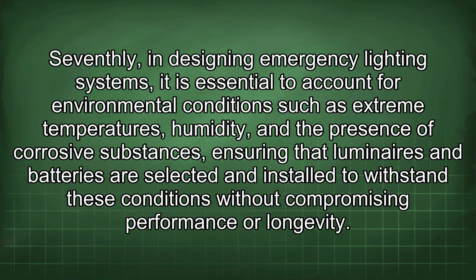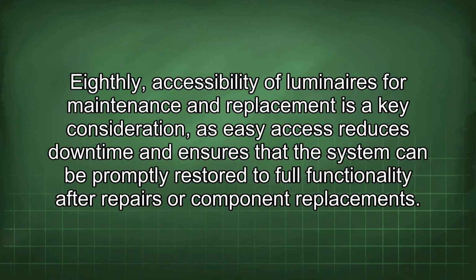Seventhly, in designing emergency lighting systems, it is essential to account for environmental conditions such as extreme temperatures, humidity, and the presence of corrosive substances, ensuring that luminaires and batteries are selected and installed to withstand these conditions without compromising performance or longevity. Eighthly, accessibility of luminaires for maintenance and replacement is a key consideration, as easy access reduces downtime and ensures that the system can be promptly restored to full functionality after repairs or component replacements.